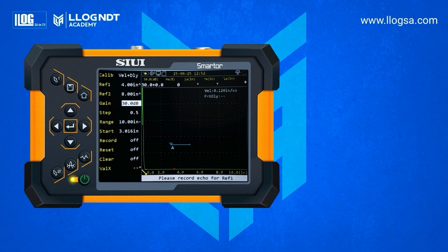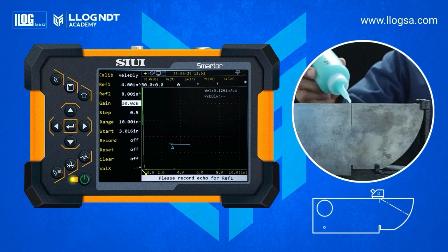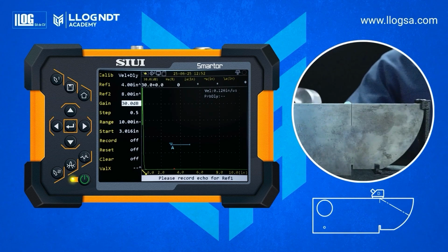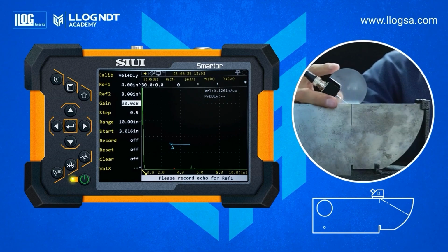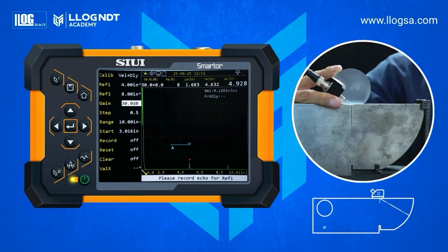We will begin with the index point verification, the exit point of the beam. Place the transducer in position D, aligning the wedge marking line with the notch on the block. Move the transducer back and forth until you find the maximum amplitude of the echo corresponding to the 4-inch radius. Once located, press F1 to bring the amplitude to 80%. Verify that both reference marks align. If the wedge line does not match the notch on the block, draw a new line on the wedge. That will be the index point of the beam exit.